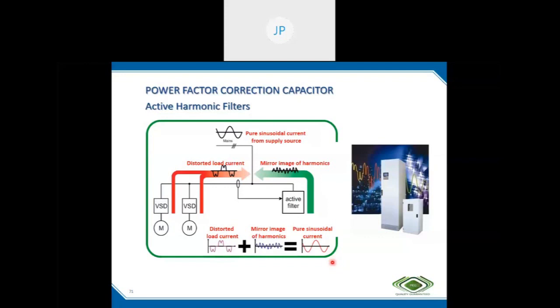Here, the difference is that a passive filter is absorbing type. Wherever there is any injection, it is absorbed and returned to the source. Here, it is generating some additional current which is opposite to the harmonics and injecting it. It needs auxiliary power and causes very high losses, and it is not actually suitable for locations with voltage distortion of more than 10%. Even manufacturers will not recommend using this at voltage harmonics more than 10%, not current harmonics.